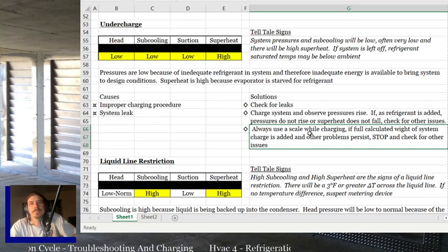Anyway, the reason the pressures are low is because there's inadequate refrigerant in the system, and therefore there's inadequate energy available to bring the system to design conditions. We can't pick up enough heat. We're trying to pick up as much heat as we can. We're picking up all the heat in the world, but it's still not enough heat. We're not raising the pressures up, so everything stays low, and our superheat's high because we've got enough refrigerant to superheat the heck out of it, but that's all we got. We just got enough refrigerant to pick up what's there, basically.